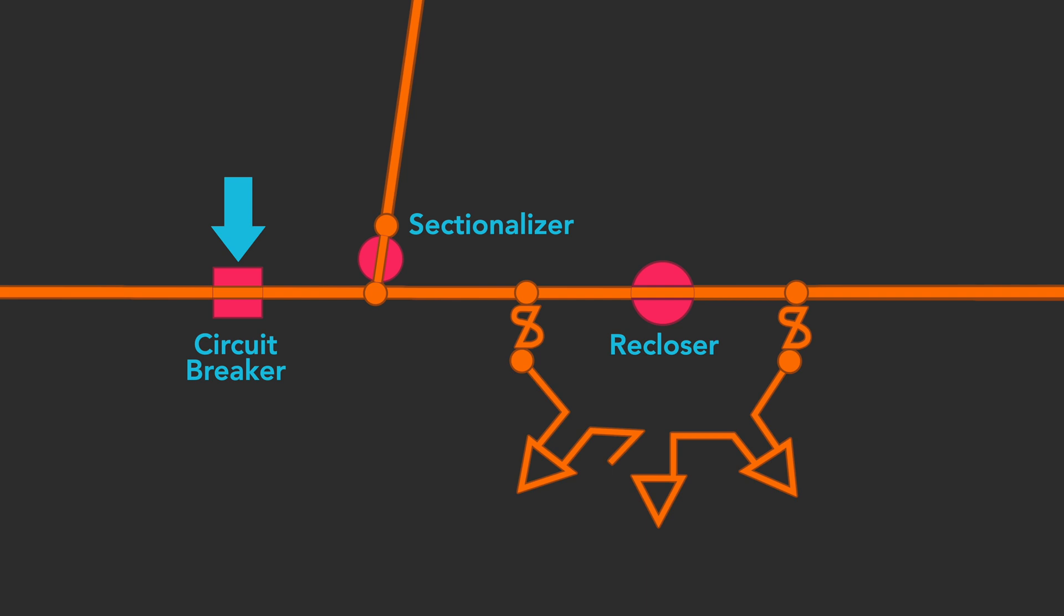This is a circuit breaker located in the substation, a feeder line, and two lateral circuits. The first is an overhead circuit connected to the feeder through a sectionalizer. The other is a URD loop system of pad-mounted transformers with each end of the loop connected to the overhead feeder through a fused cutout switch.